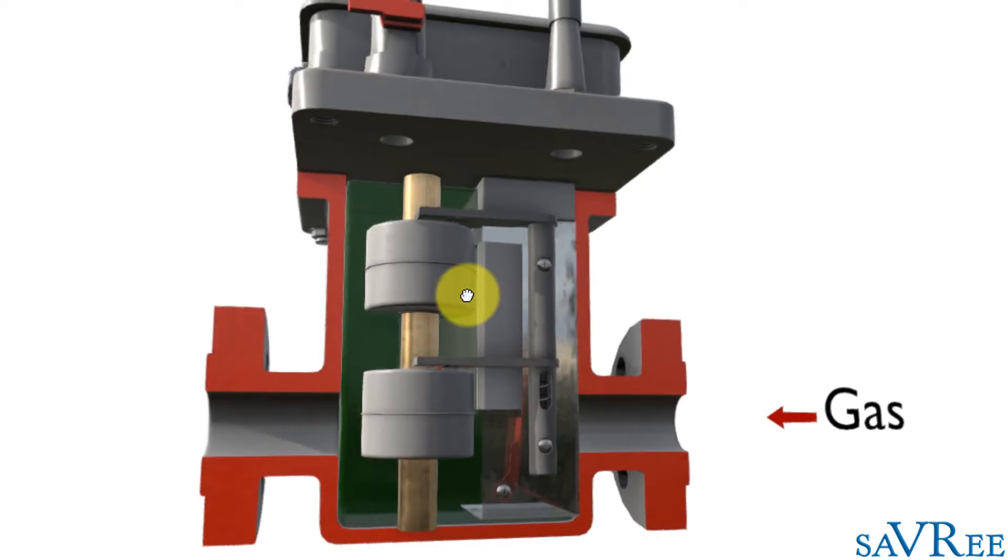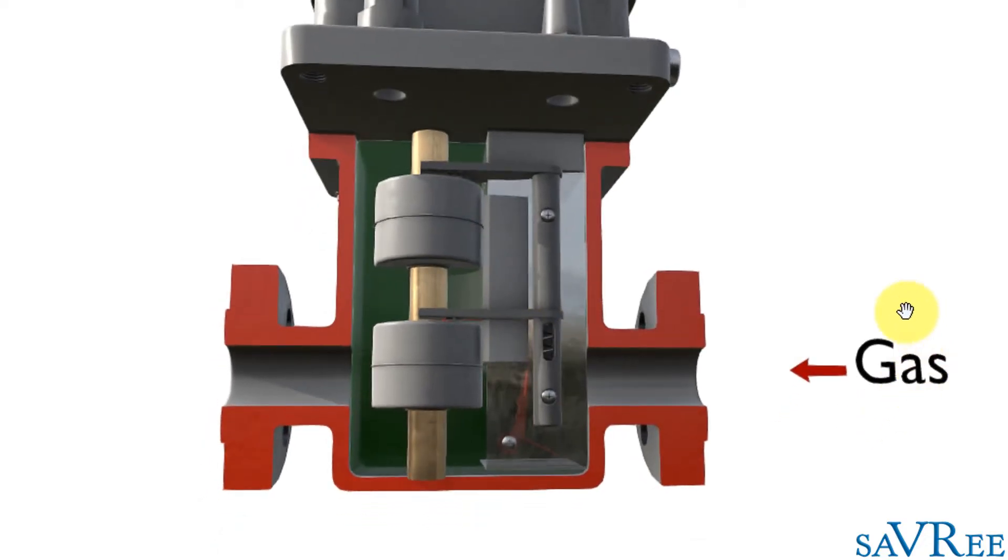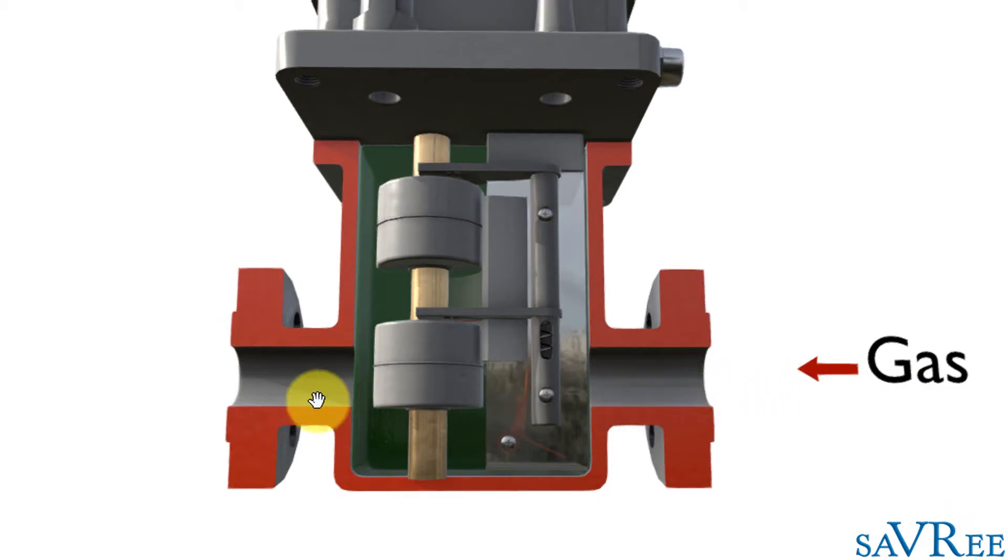So what is it doing? Well, gas, as you can see on the right-hand side, flows out and along this pipe from the main tank to the conservator. Normally, there should not be any gas within the transformer itself.